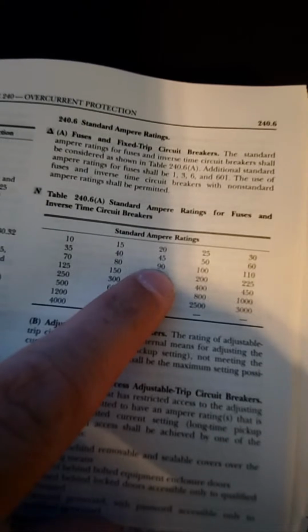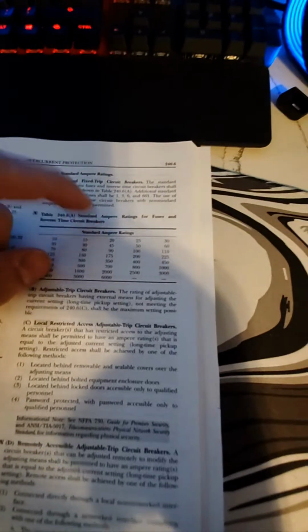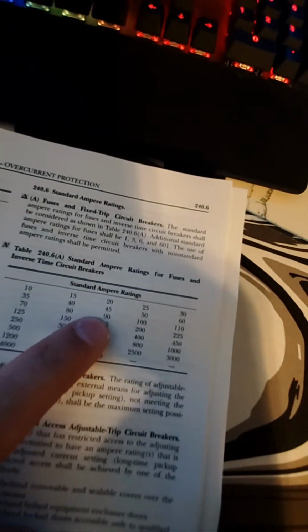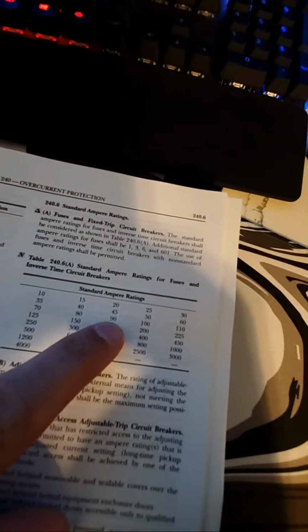So the problem with that, you can't go to the next standard size, because if we look at 240.6 here, you're going to see 90 is a standard. The rules say you can go to the next standard size if you're in between one of these. So if we were 87 amps, we go to 90. If you were 95 amps, you go to 100. But if you're 90 amps and your wire's only good for 90 amps, you can't put on a 100 amp breaker. Absolutely true, Shaka. I didn't know you knew that, buddy.